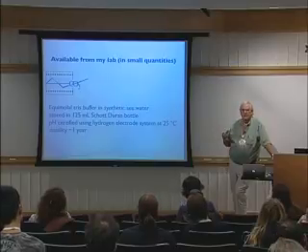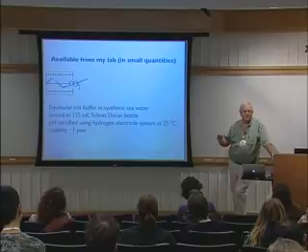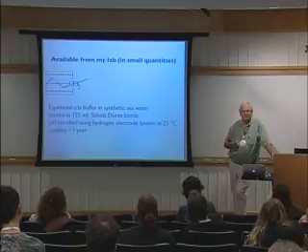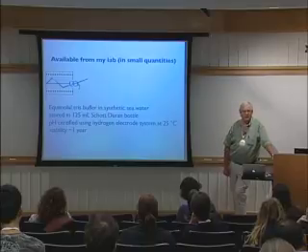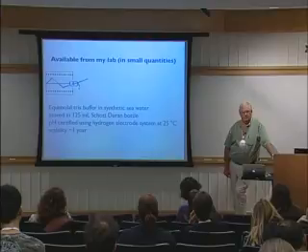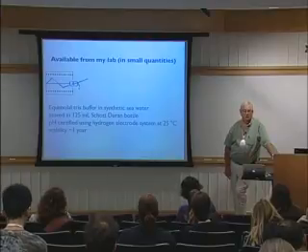But this is the difficulty. If you're using electrodes, you always have to have a buffer there. And so you always have to calibrate. So probably you have to make up your own pH buffer. But if you got some of this, you compare the two and say, yeah, I made it up okay, or no, it's 0.01 higher than what it ought to be, but it's 0.01 higher yesterday and tomorrow, so I can allow for that.